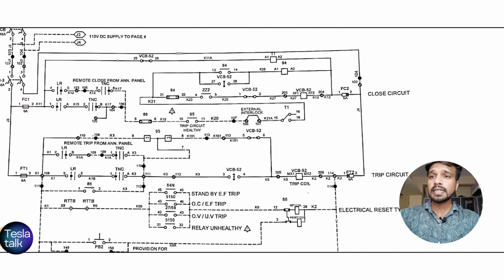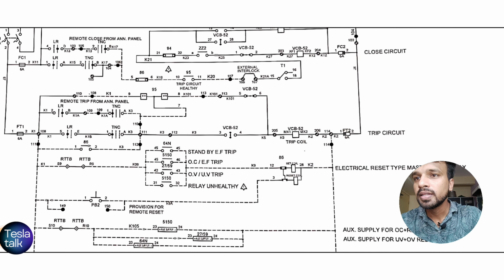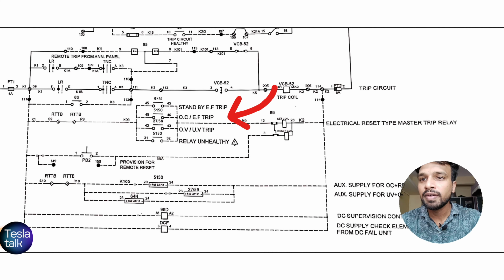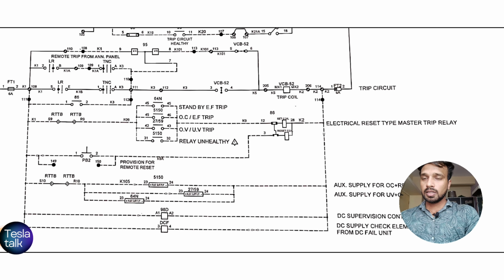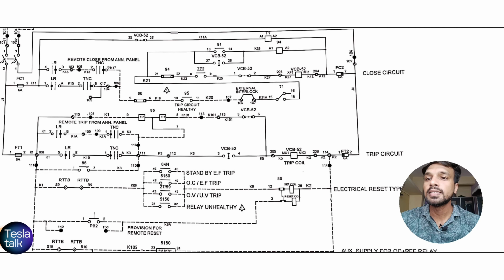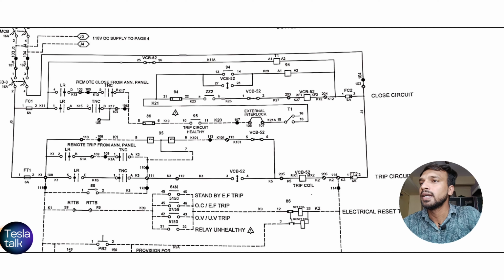So we can see here there are some relays. There is a standby earth fault relay, overcurrent and earth fault relay. In the previous video we have seen that these relays were not present in the VCB schematic, the breaker schematic, but this is a control and relay panel schematic which includes both.